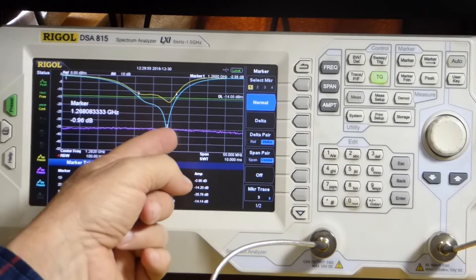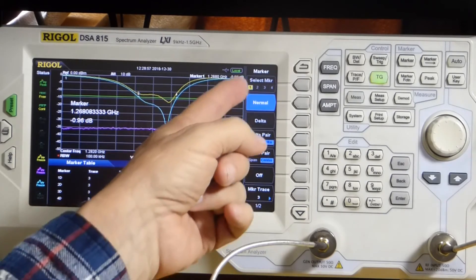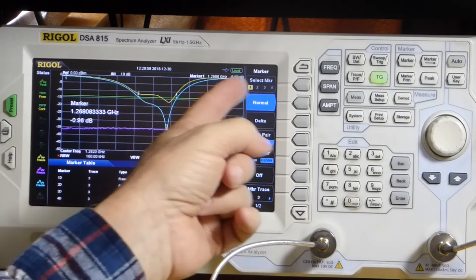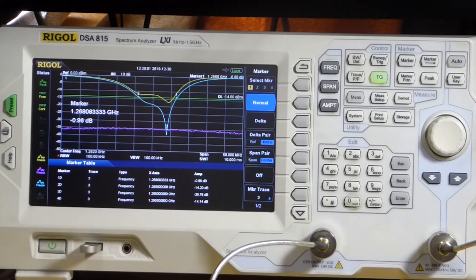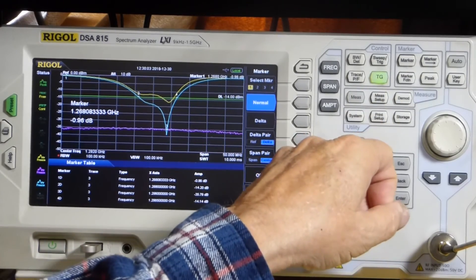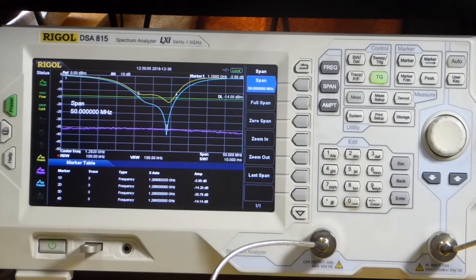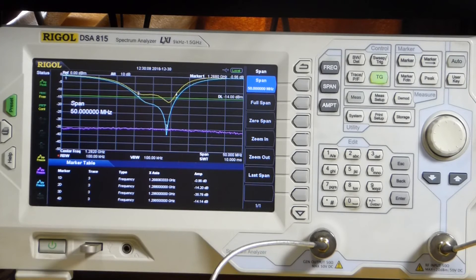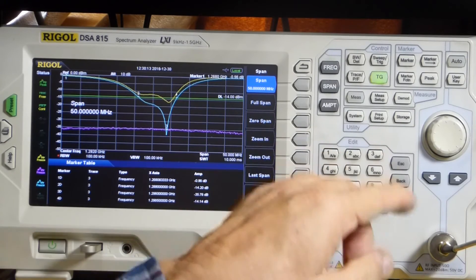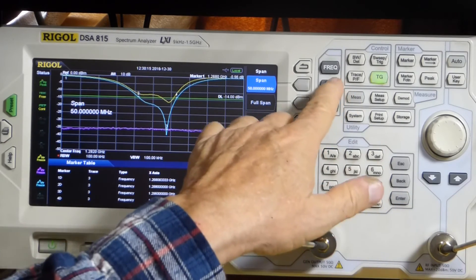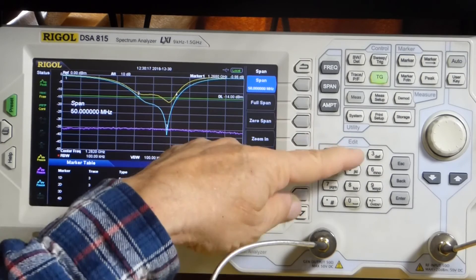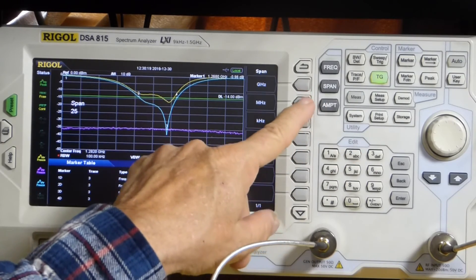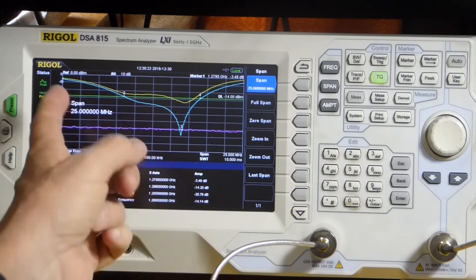So now you see that even though this is over here now, we do have the total response here. And again, I can go back to span here and up to the limit of the point at which things start to pixelate, this will work fine. Let's go to a span of not 50, but 25 MHz. There you go.